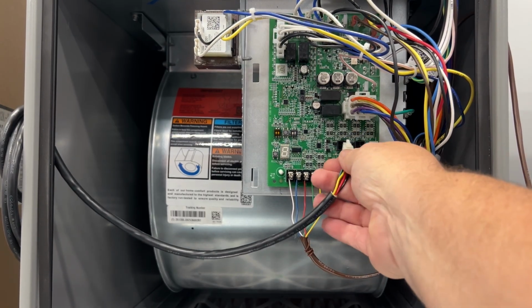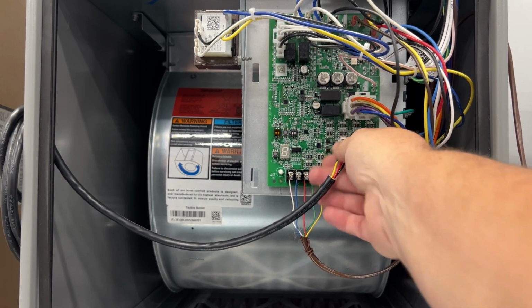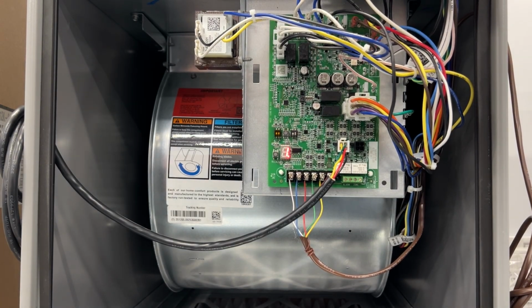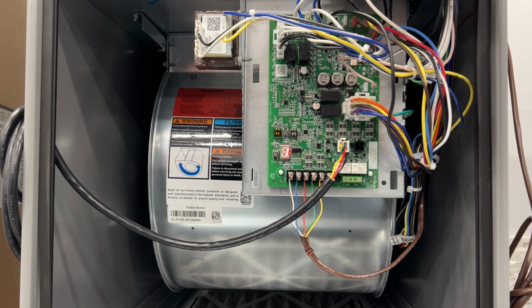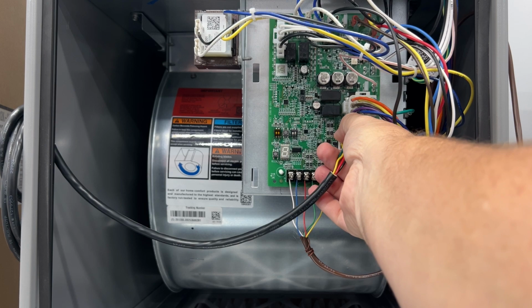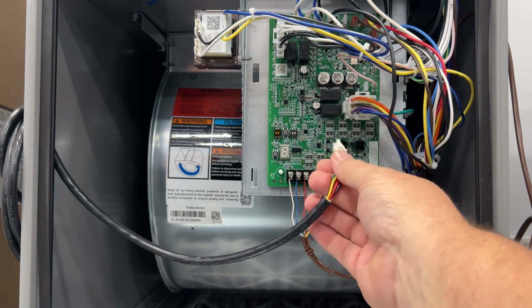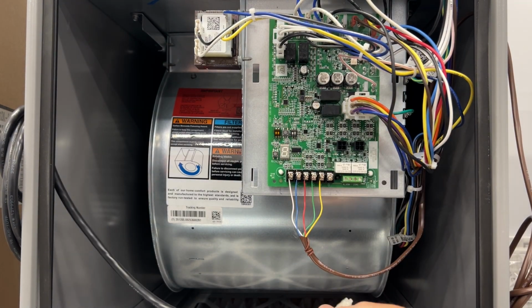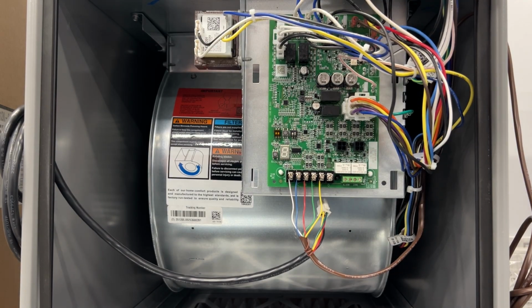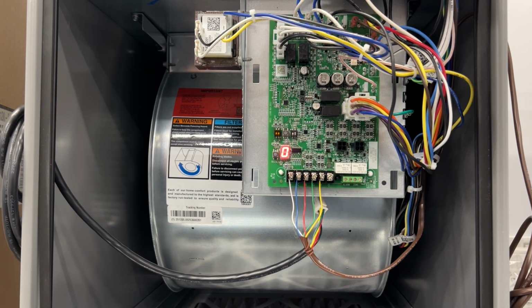If you put it in the wrong location and you start the machine up, you'll get an error code almost immediately. You'll see an E followed by an error code. In this case, it's 154. And in that case, you know that you have put it in the wrong location or you have something wrong with your dip switches. Also, if you do not have the wire in at all, you will get an error code. The same one, I believe.